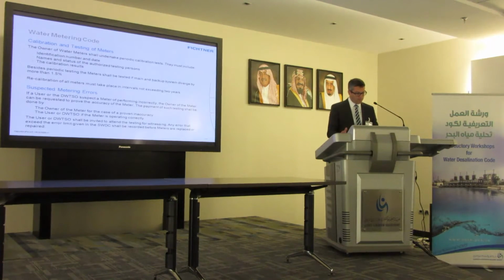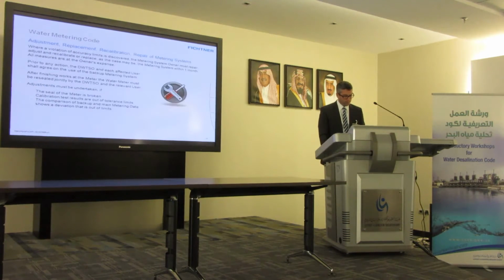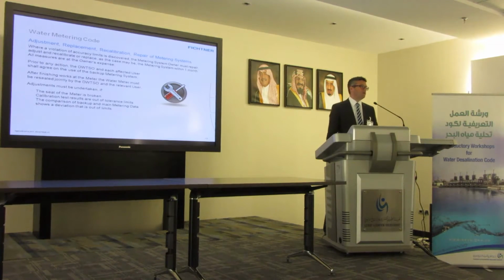Yes. In any case, when a calibration test is carried out, the other user shall be invited to witness the test, to provide clarity and transparency. Where a meter is out of the accuracy limits, the meter system owner shall repair, adjust, and recalibrate or replace such a meter within a one month time period. It shall be done basically as soon as possible in order to have again the basis for correct measurements.